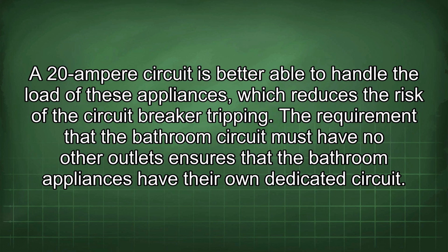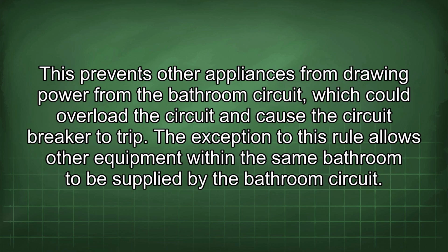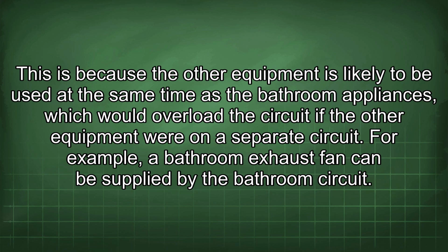The requirement that the bathroom circuit must have no other outlets ensures that the bathroom appliances have their own dedicated circuit. This prevents other appliances from drawing power from the bathroom circuit, which could overload the circuit and cause the circuit breaker to trip. The exception to this rule allows other equipment within the same bathroom to be supplied by the bathroom circuit. This is because the other equipment is likely to be used at the same time as the bathroom appliances, which would overload the circuit if the other equipment were on a separate circuit. For example, a bathroom exhaust fan can be supplied by the bathroom circuit.